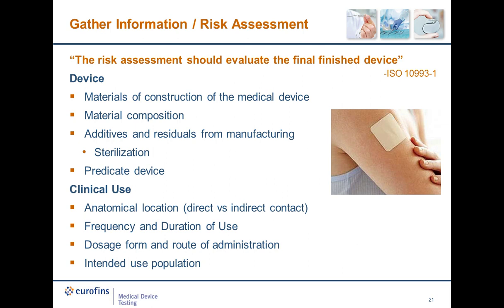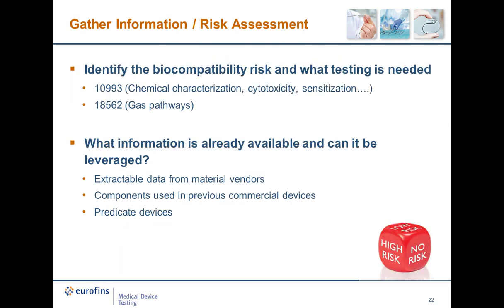The anatomical location is important information, as well as other details pertaining to clinical use, like duration of use, dosing, and intended use population. Finally, an applicable predicate device can be extremely useful during the chemical characterization process. If there is a potential predicate device, the same information on the predicate device pertaining to the composition and clinical use of the device should be obtained.